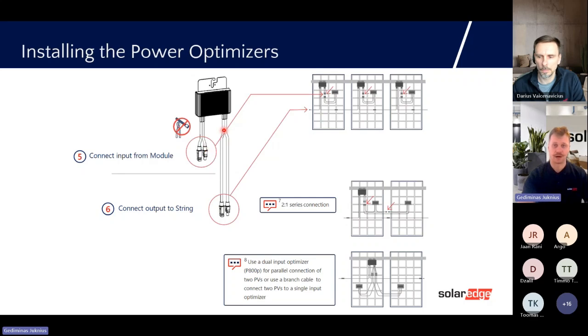Here are also examples of how you can connect one optimizer per PV module or one optimizer per two PV modules. Basically you connect the panel plus and minus to the optimizer, and then you connect the optimizers in series. For those who never installed the commercial one with a 2-to-1 connection, it's basically connecting panel plus and minus together, and then plus and minus to the optimizer. And again, you're connecting in series. We do not produce optimizers to connect in this way anymore. This is just what we used to do in the past.